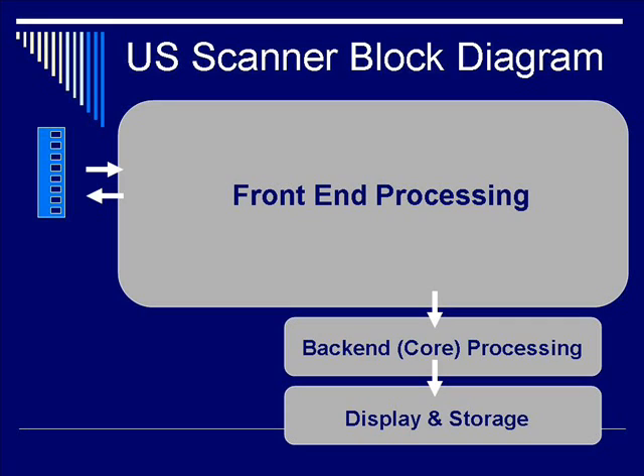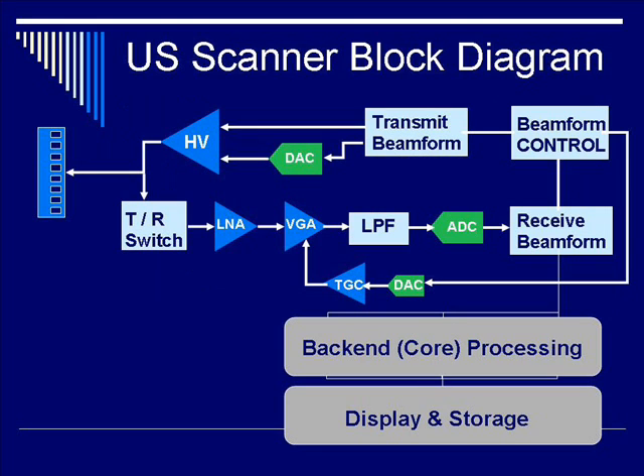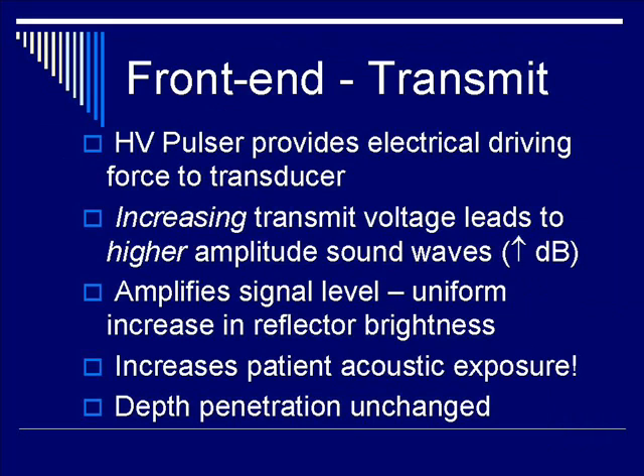Now let's peel off the block bit by bit. With an eight-element transducer example, peeling off the front-end processing block reveals the upper line as transmission and the second line as the receiving aspect. In front-end transmission, a high-voltage pulser provides the electrical driving force to drive the transducer to produce the ultrasound pulse. Increasing the transmission voltage leads to high-amplitude sound waves and increased decibels. Amplifying the signal level yields a uniform increase in reflected brightness. However, increasing transmission power also increases patient exposure to sound waves, and depth penetration is unchanged.